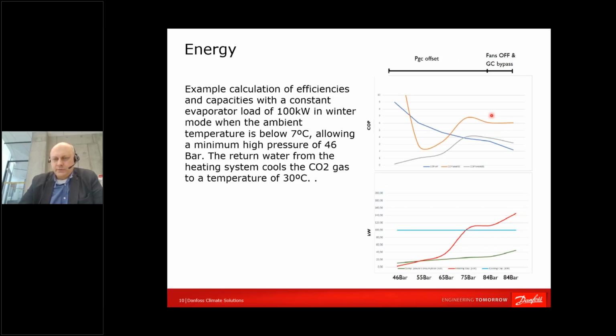How does it land with, somebody would ask, COP, or coefficient of operation performance? Here you can see that if we are having a system with a power of 100 kilowatts, and we are pumping more pressure, here the green one is the consumption of electricity. Here we can see our heating COP. It's increasing. So we may say that we might reach the best performance somewhere around 75 bars and so on.